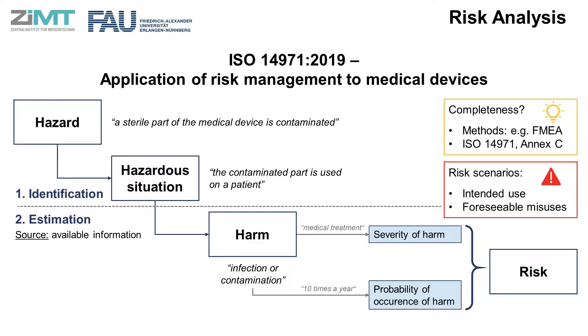It is not an easy job to cover all the risks in the analysis, especially with consideration of risks arising from different life cycle phases. Systematic methods like Failure Modes and Effects Analysis (FMEA) can be helpful at this point. ISO 14971 also lists examples of hazards in Annex C, which can be used as a reference for a particular risk analysis. It is important to note that ISO 14971 explicitly states that the risk analysis should not only be applied to the intended use — foreseeable misuses should also be taken into account.